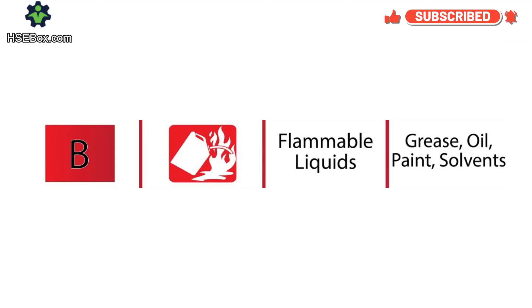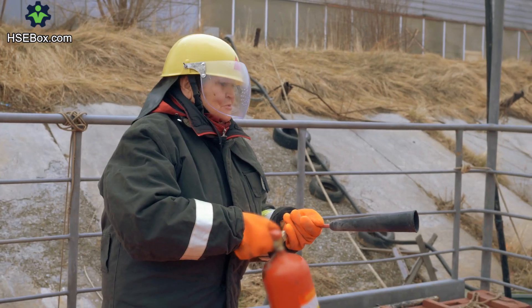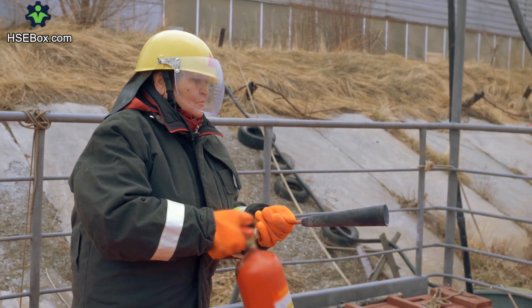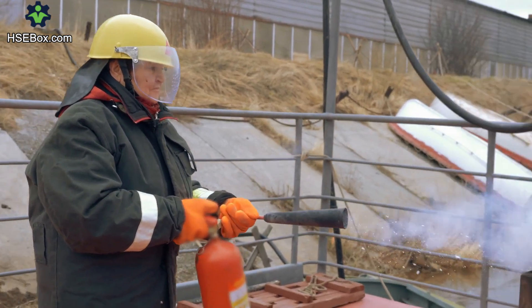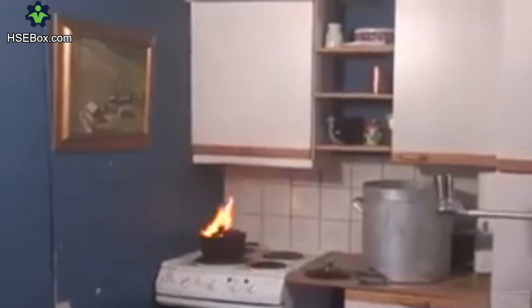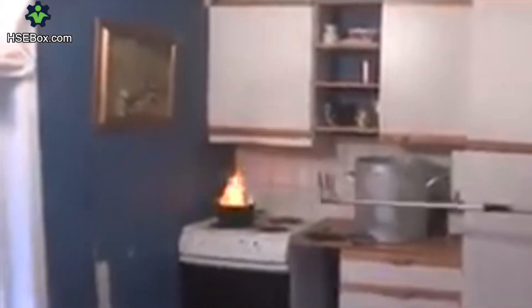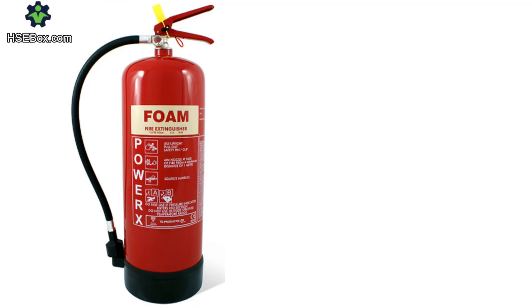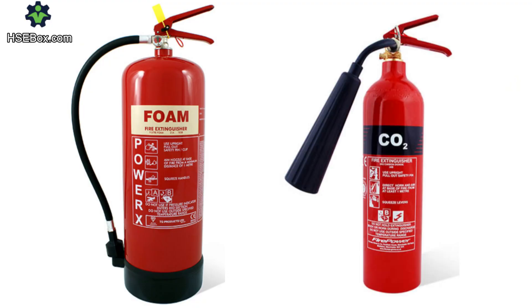Moving on to class B fires, these involve flammable liquids such as gasoline, oil, and paints. Class B fires are particularly dangerous because they spread rapidly, and using water to extinguish them can make things worse by causing the burning liquid to splash. For these fires, you need foam or carbon dioxide extinguishers.